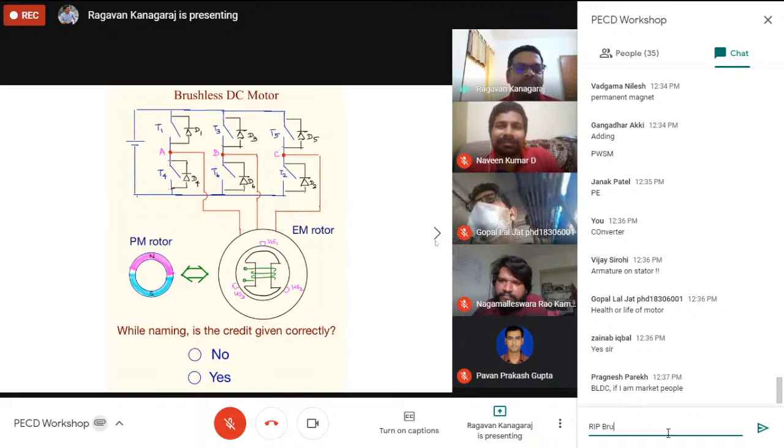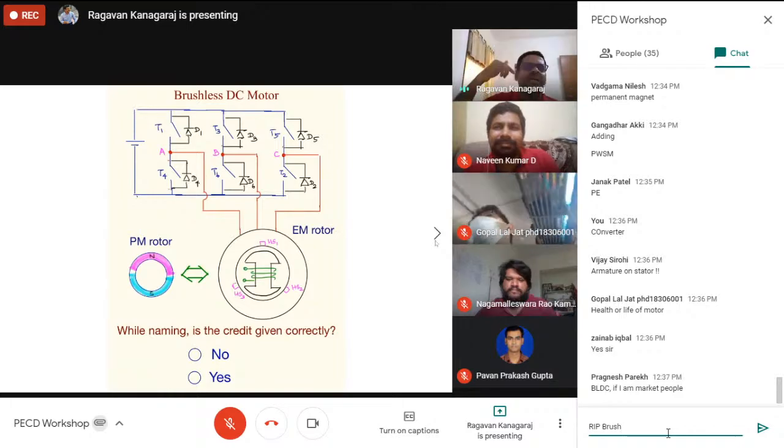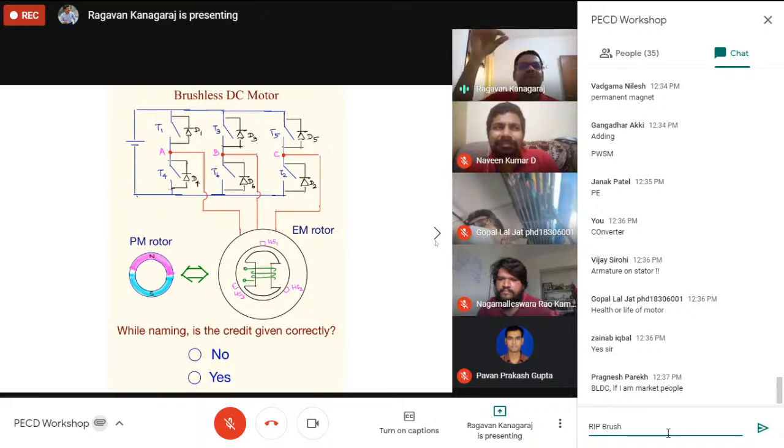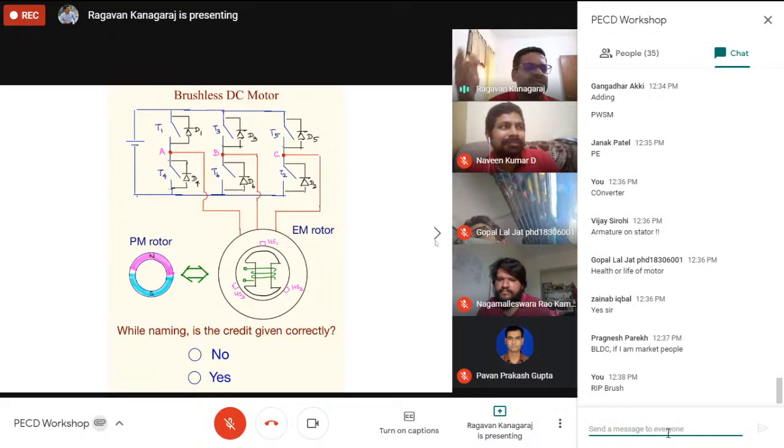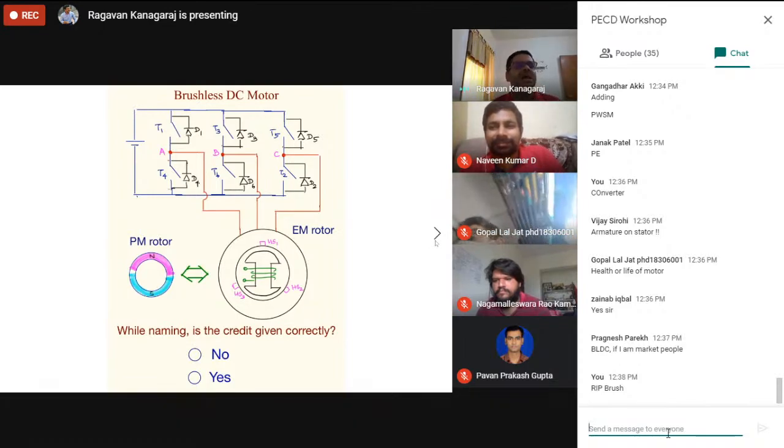Similarly, the main problem was the sparking that was happening in the commutator. Why in the commutator? Because you have the segments which are separated by insulator. What is a commutator? It's not a continuously conducting cylinder. You have many segments corresponding to the number of conductors terminating to the commutator. The segments are separated by insulator. So whenever the brush is touching, and after some time the commutator segments leave, there is a current interruption, because insulation comes. Whenever there is a current interruption, a spark is developed. Also, there is a shift of the magnetic neutral axis with armature reaction.